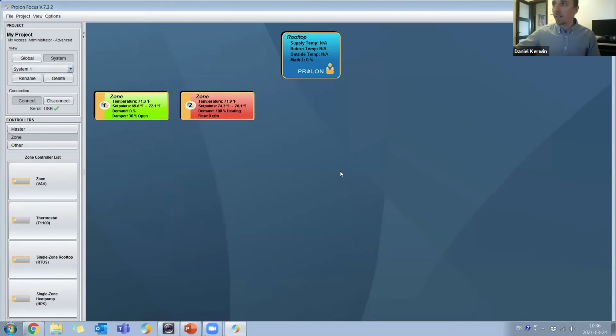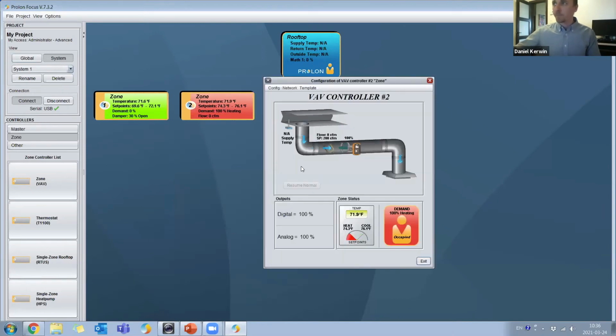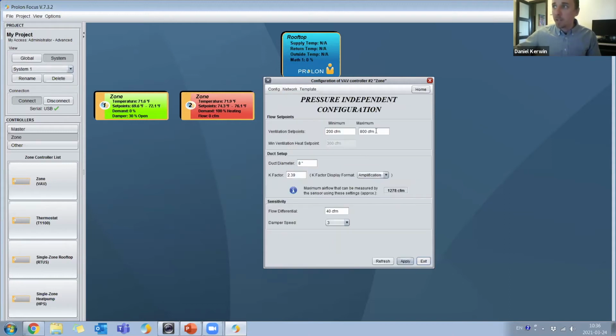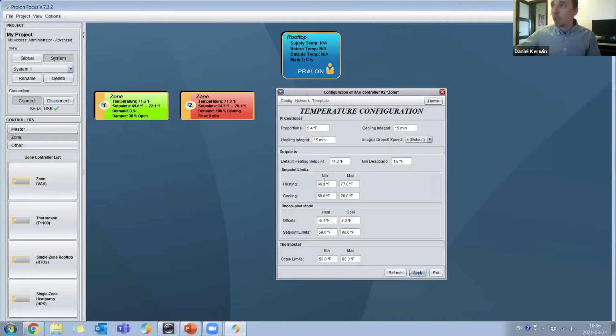If I go take a look at the other zone right here, it's almost the same graphic, but we do see that it does have the flow sensor. So we know that it is the pressure independent version. And then I can just go onto that menu. And then here we can set what are the minimum CFM, maximum CFM with the K factor and the duct diameter for the balancing. All right. We are able to input set point limits as well. So if we want to lock people in within a certain range of set points, we can do that. Or if we want to give them a very wide range as well. So it really depends on the application.